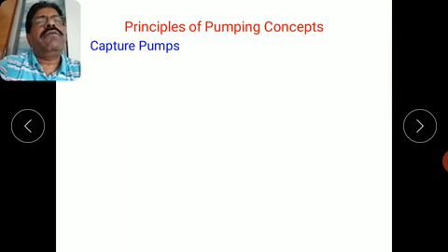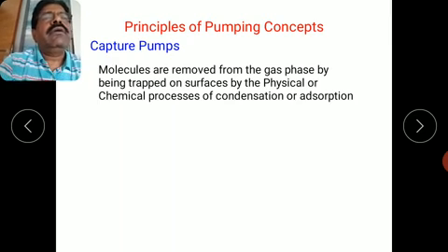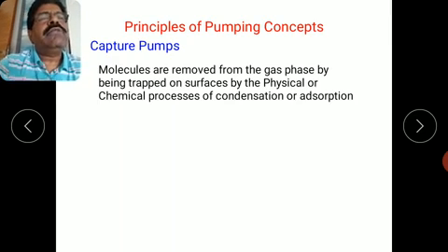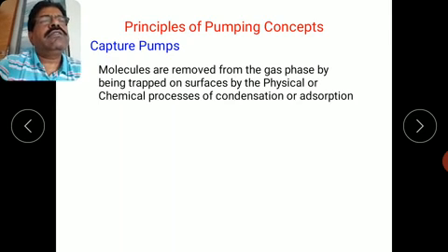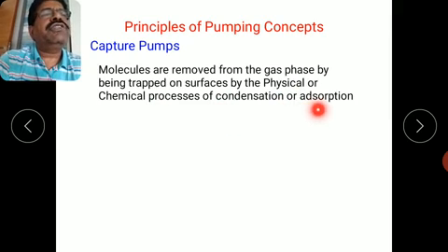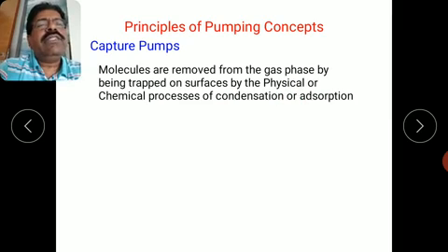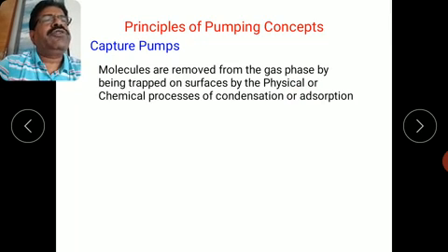Then the third basic principle of operation of the vacuum pumps, that is the capture pump. So let us see what these capture pumps are. In capture pumps, molecules are removed from the gas phase by being trapped on surfaces by the physical or chemical processes of condensation or adsorption. So now in this case, the gas molecules are captured. They are trapped on surfaces by physical or chemical processes like condensation or adsorption.